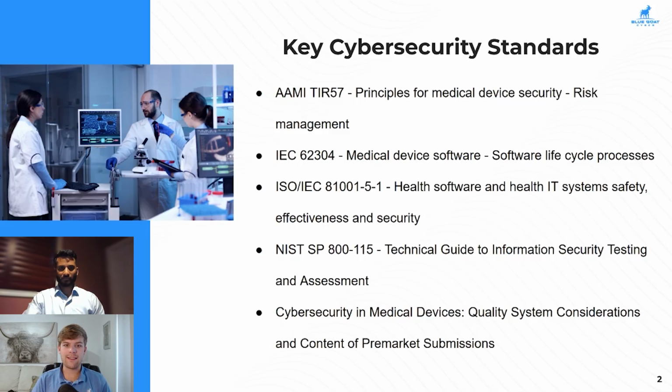Next, we're looking at IEC 62304, Medical Device Software Lifecycle Processes. This talks about the development flow for ensuring that we're designing safe and secure medical device software. Very similar standard is ISO IEC 81001-5-1, Health Software and Health IT System Safety, Effectiveness, and Security. This talks a little bit more about the controls and implementation based on the lifecycle.